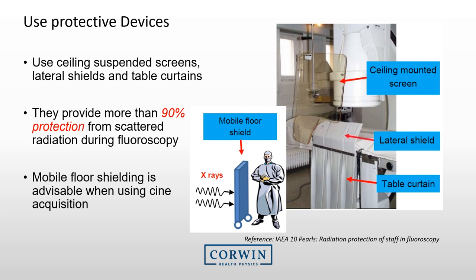There are usually additional lead protective devices within the room. A ceiling-mounted lead protective screen can be dropped down to reduce exposure to your face. Additionally, table curtains and a lateral shield can be positioned around the table. Once all of these are in place, the radiation exposure to the operator is reduced significantly. A mobile floor shield may also be provided for those near the patient, offering further significant radiation reduction during fluoroscopy.